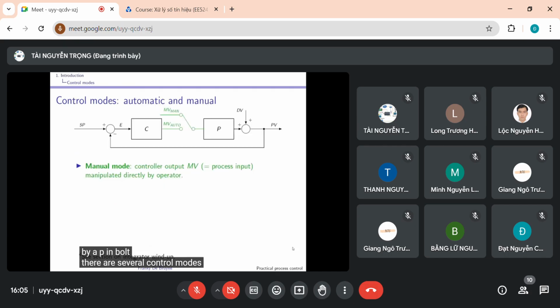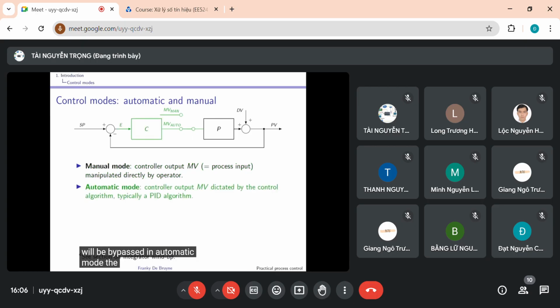There are several control modes associated with the controller, and as I said before, this controller will very often be simply a PID controller. Well, the first choice that we have is to put this controller in automatic or in manual. In manual mode, the controller output MV is directly manipulated by the operator. And this can be done, for instance, by changing a value MV in the human-machine interface to directly influence the process input. In manual mode, the control algorithm, and very often the PID control algorithm, will not be used. In automatic mode, the controller output is dictated by the control algorithm, typically, as I said, a PID control algorithm.